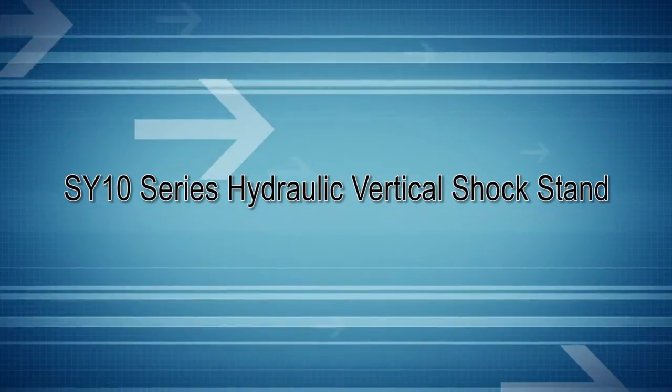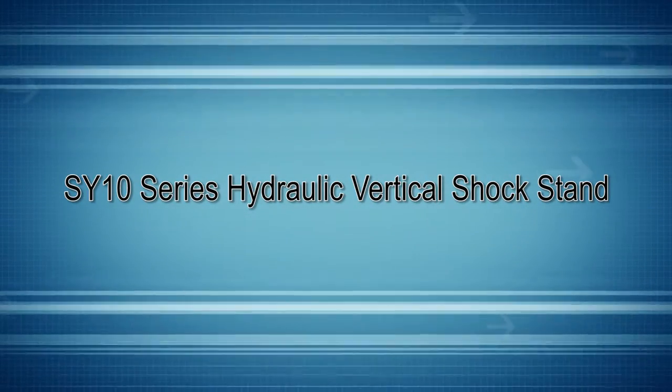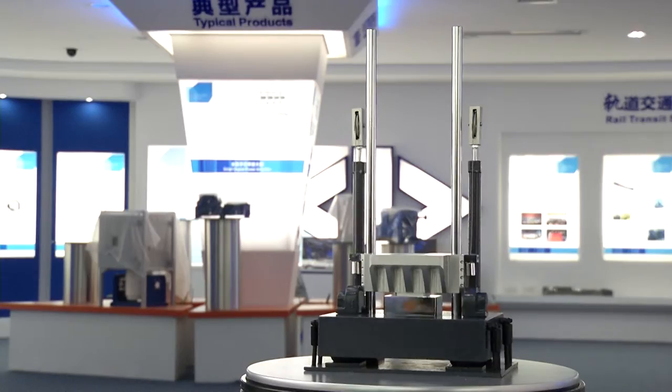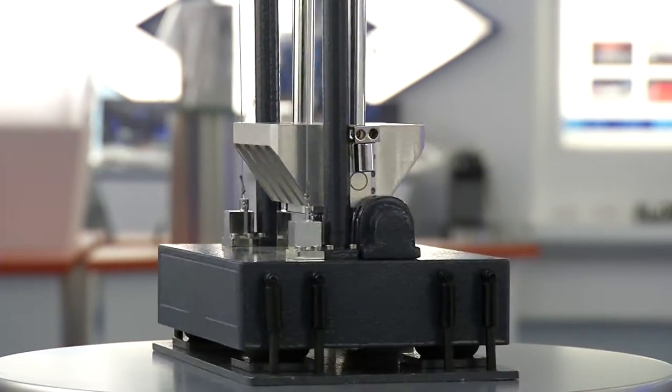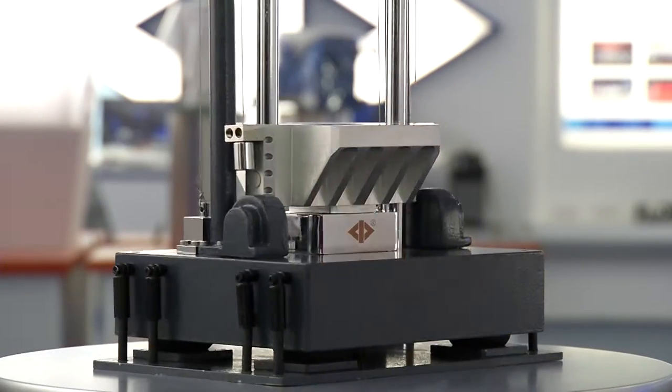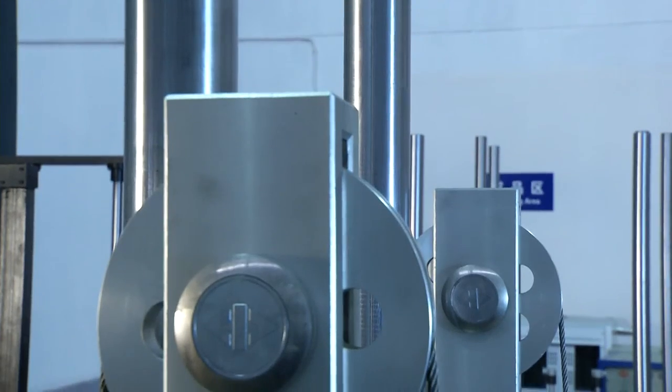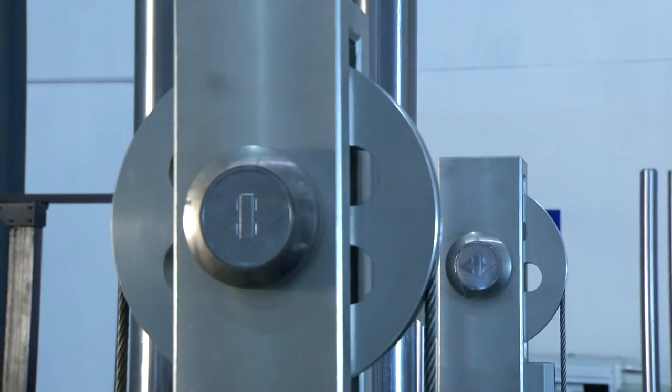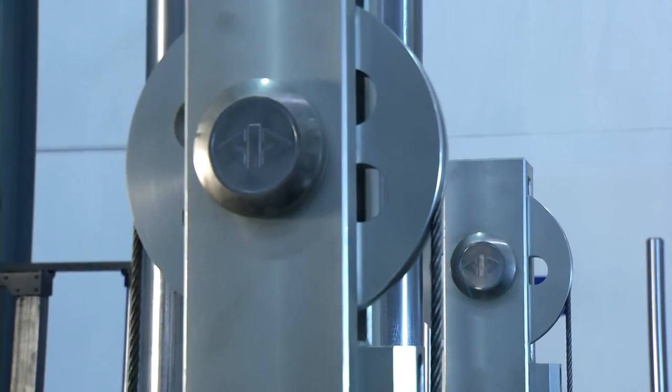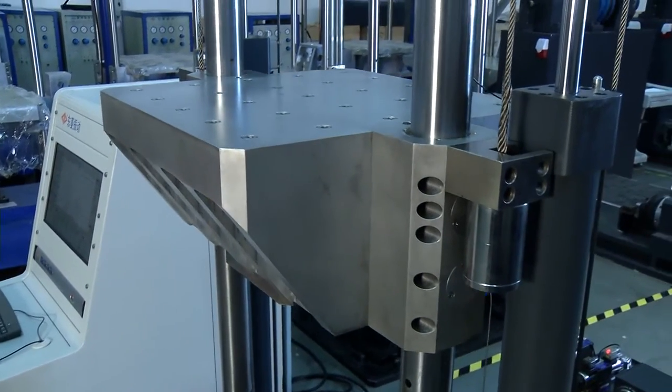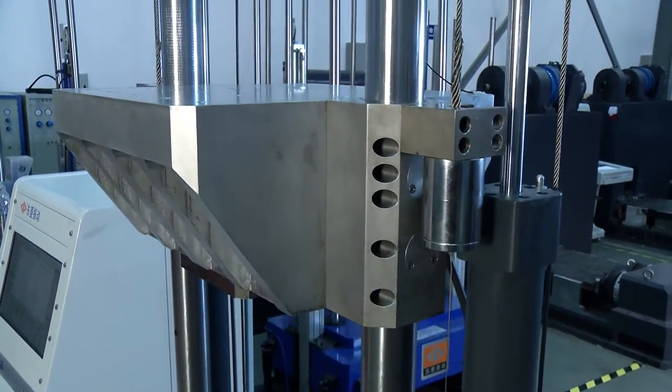SY10 Series Hydraulic Vertical Shock Stand is mainly used in simulating the shock suffered in practical conditions when mechanical and electrical products are in transportation or operation. It can verify the function reliability and structure integrity of the product in shock environment.